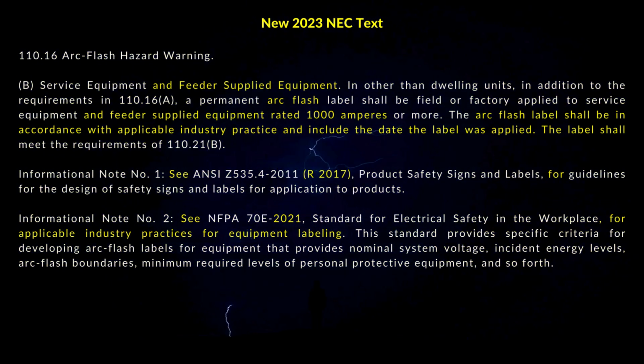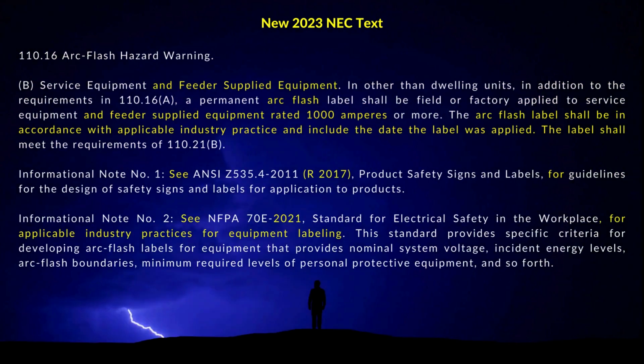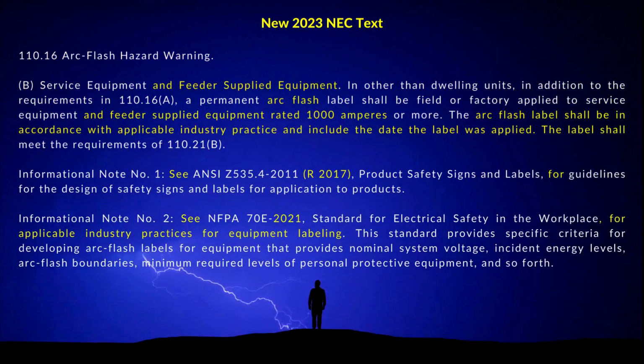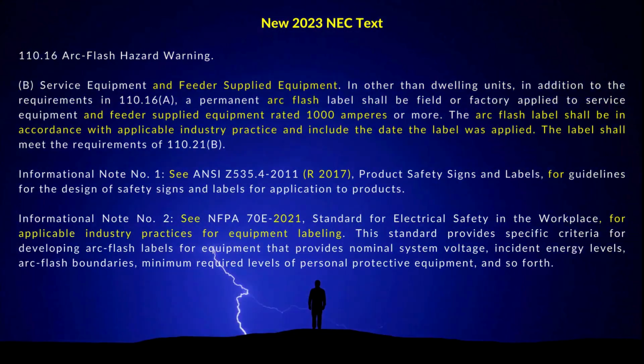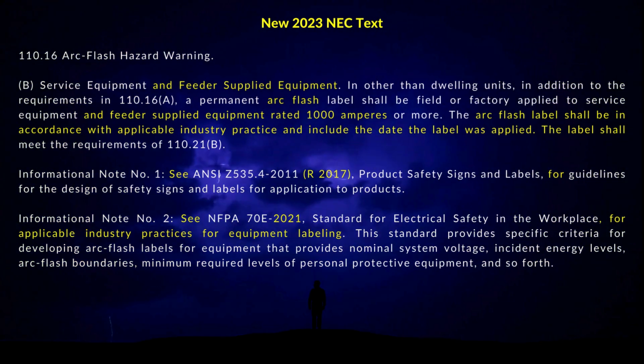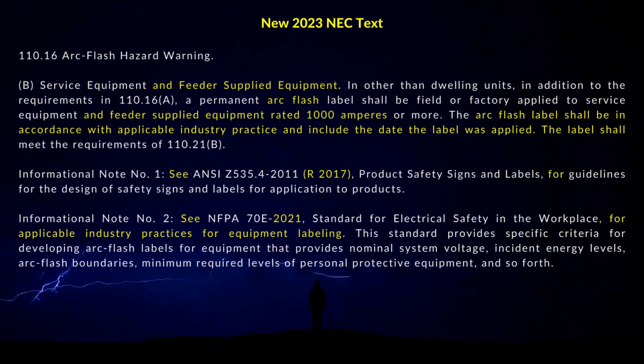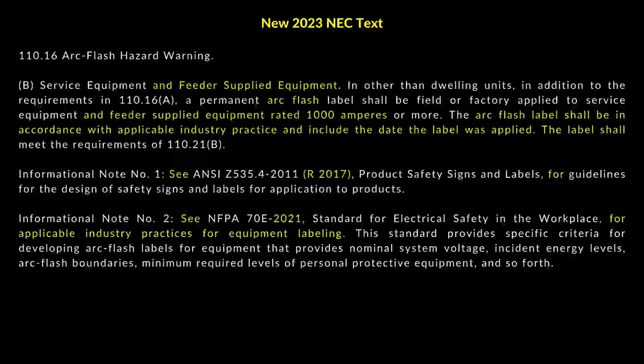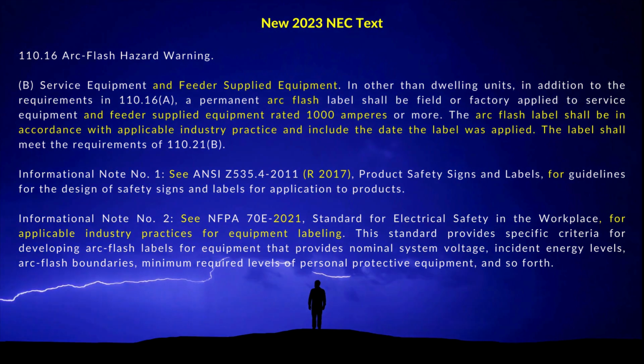Informational Note number 1 states: see ANSI Z535.4-2011 (R2017), Product Safety Signs and Labels, for guidelines for the design of safety signs and labels for application to products. Informational Note number 2 states: see NFPA 70E-2021, Standard for Electrical Safety in the Workplace, for applicable industry practices for equipment labeling. This standard provides specific criteria for developing arc flash labels for equipment that provides nominal system voltage, incident energy levels, arc flash boundaries, minimum required levels of personal protective equipment, and so forth.